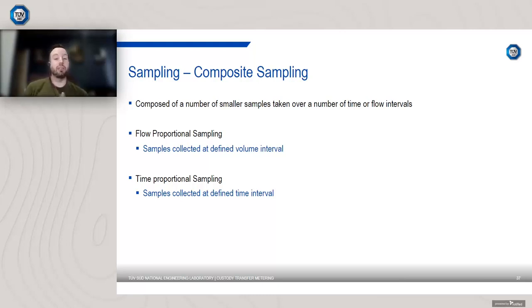Composite sampling is again really important. This is where a sample is composed of a number of smaller samples taken over time or flow intervals. Obviously in a metering system, conditions are not going to be fixed at one flow rate for the entire time. Conditions will change, temperatures and pressures will change. In order to have a sample that's representative of these changing conditions, you need to use composite sampling.